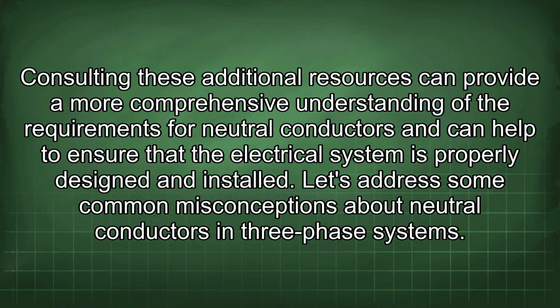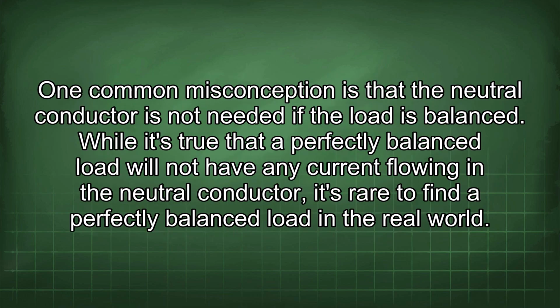Consulting these additional sources can provide a more comprehensive understanding of the requirements for neutral conductors and can help to ensure that the electrical system is properly designed and installed. Let's address some common misconceptions about neutral conductors in three-phase systems. One common misconception is that the neutral conductor is not needed if the load is balanced.